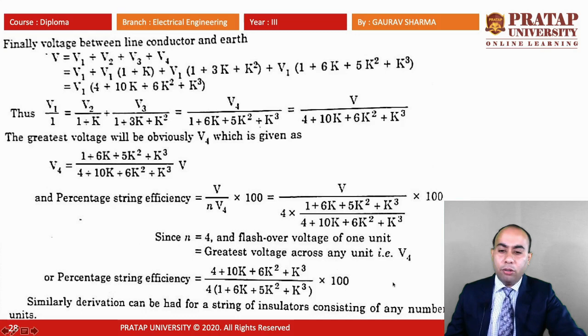So now the percentage string efficiency is equal to V divided by n into the voltage across the nearest-most unit, V4. We put the values, where n is equal to 4, and we get the percentage string efficiency by this formula. Now this string efficiency has to be improved, so we have methods by which we can improve the string efficiency.